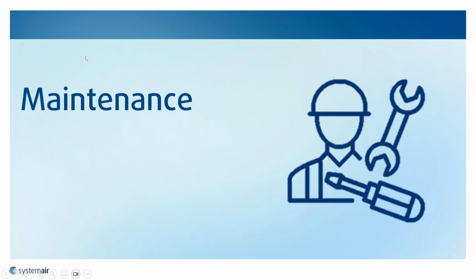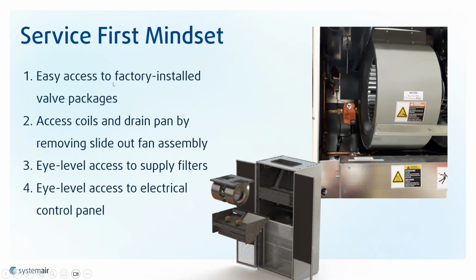Maintenance. Maintenance is really special here, because we put everything at eye level, or everything, sorry, is easily accessible in the cabinet. You have easy access to factory installed valve packages, right? Just a hand's reach away. If you need any shutoffs here, you've got isolation valves, manual circuit balancing valves, just at a hand's reach away. You could access the coils, right? Your evap coil, condenser coils. This whole fan module slides out. You just undo the wing nuts and remove that wire, and then it slides out for easy maintenance in case you need to replace a motor or a fan.